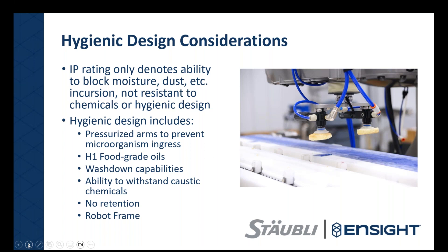A lot of customers get caught up thinking everything has to be IP69K for a primary side application. IP rating really only discusses pressure and water — IP67, and even some IP65 depending on how it's put together, is perfectly acceptable for primary side applications and works just fine. The industry trend toward IP69K is strong, but some things aren't available there yet, and customers don't have to require IP69K.